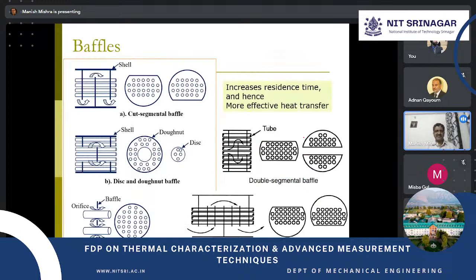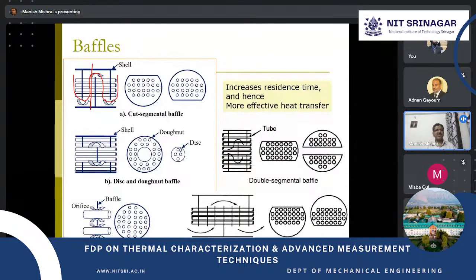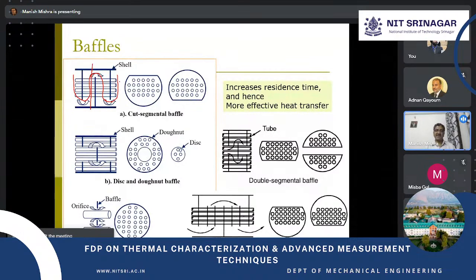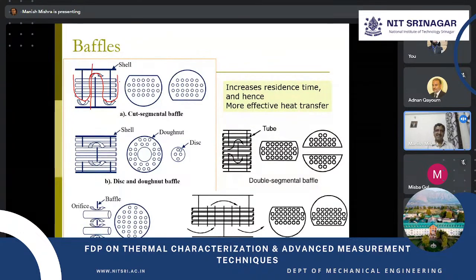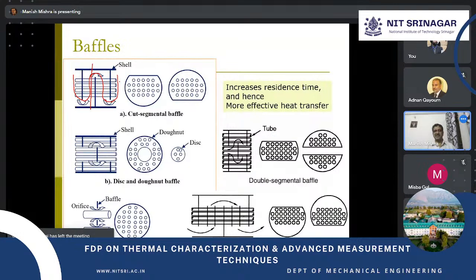There are various types of baffles. Apart from increasing residence time, they also create turbulence. For example, the fluid entering here goes like this, further like this, instead of entering from the top and going straight to the bottom — traveling only the width of the shell — it now travels 4 or 5 times that width. So total residence time increases by 5 times, increasing the chances of heat transfer, and the effectiveness of the heat exchanger increases.